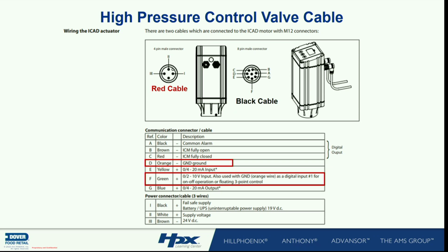Excuse me. Now to start that rack back up, what do you got to do? You've got to get that vessel pressure below 40 bar, 580, right? So I always tell everybody, bleed it down to 550, turn the rack back on, it'll start itself up. Because if it doesn't, above 40 bar, all the lights are gonna blink. 326A is gonna keep that controller at 0. And remember, you have to understand what your set point is because they're not always gonna be 326As, because the 326As are going to sundown mode. Have you seen S20 alarm?